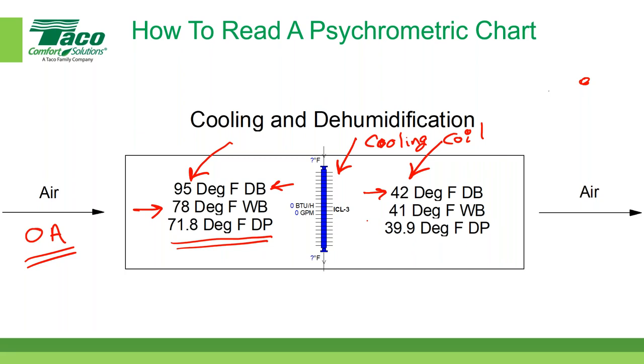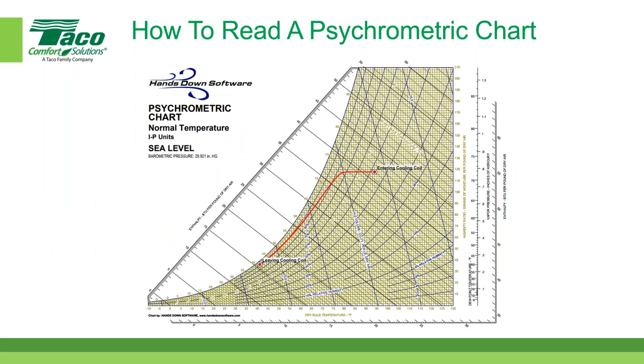And so you can see that the dew point temperature is going to drop. Rather than trying to plot it out this time, I've actually plotted it previously, so we have a nice picture. So there's our entering the cooling coil, which we said was 95 and 78. That's 95 degrees.